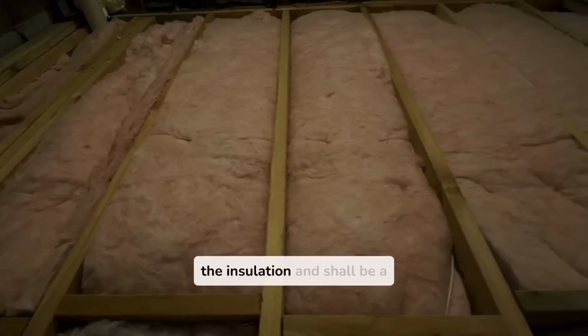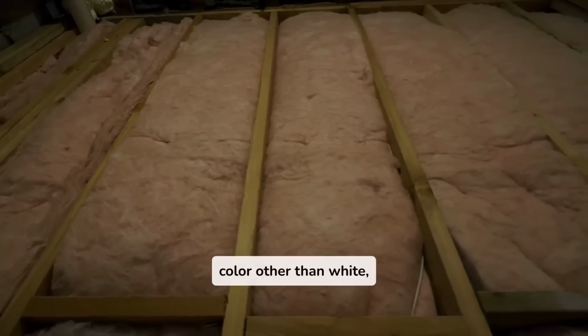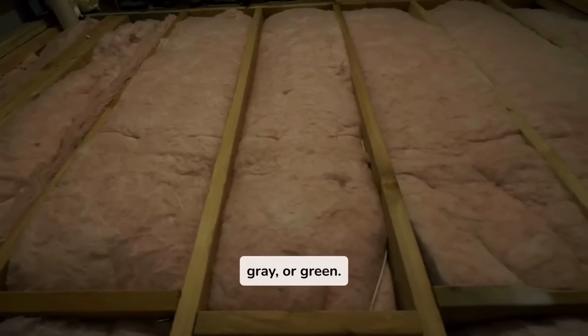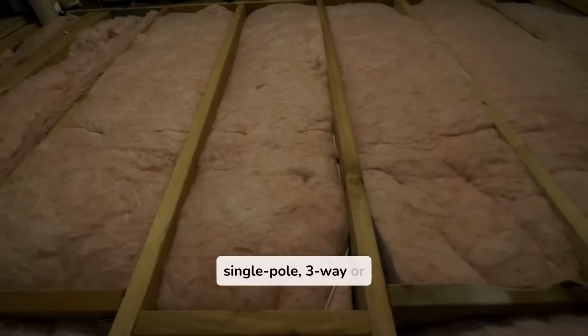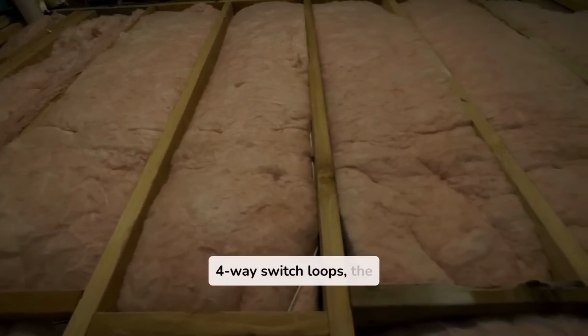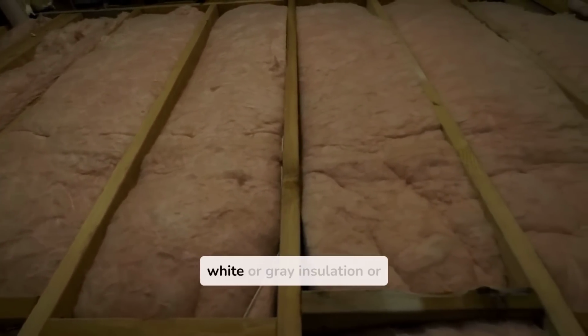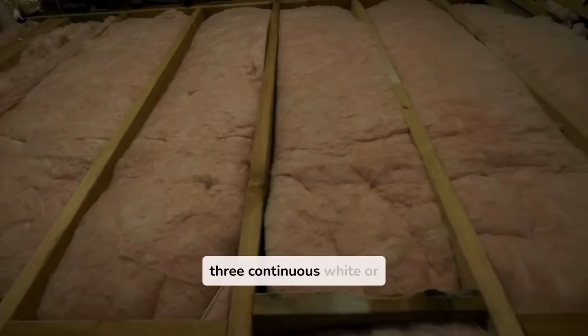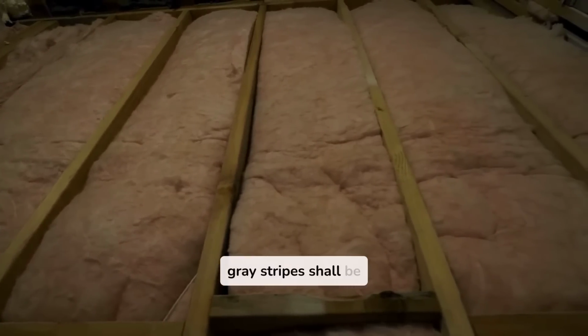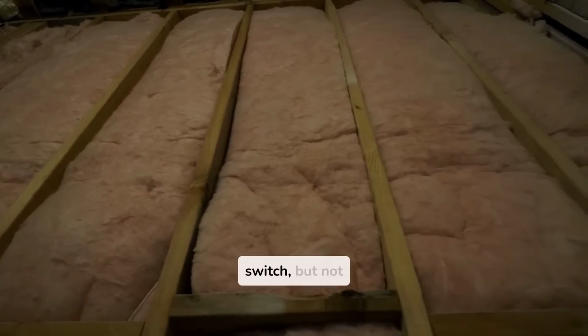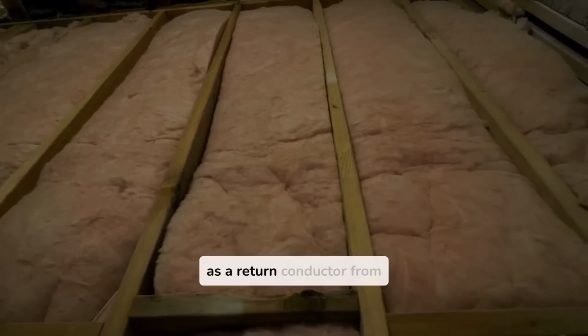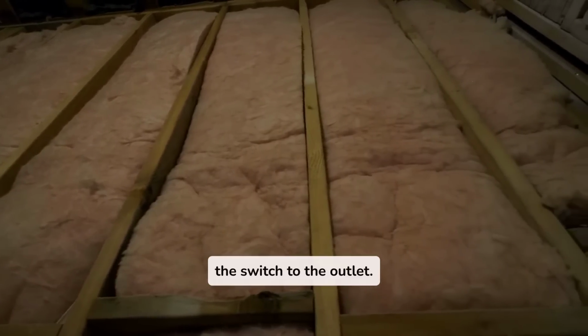Identification shall encircle the insulation and shall be a color other than white, gray, or green. If used for single pole, 3-way or 4-way switch loops, the re-identified conductor with white or gray insulation, or three continuous white or gray stripes, shall be used only for the supply to the switch, but not as a return conductor from the switch to the outlet.